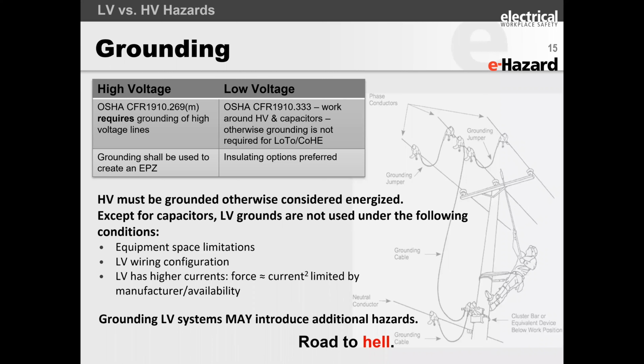The low voltage rules say that grounding is not required for lockout tagout and insulating is preferred, right? So high voltage person goes in there and says, well, I mean, what harm am I going to create if I just connect everything together and connect it down to ground? Because that is what we do at high voltage.